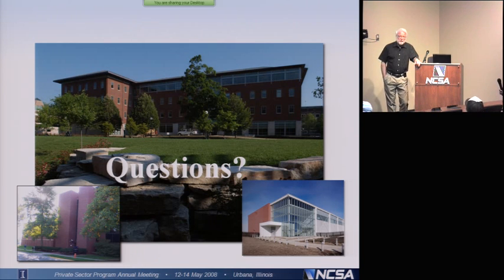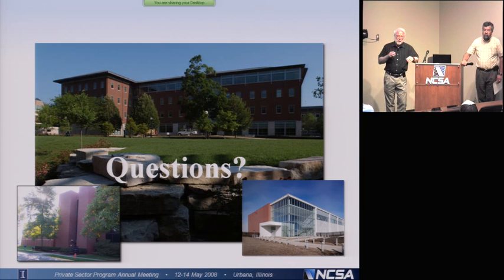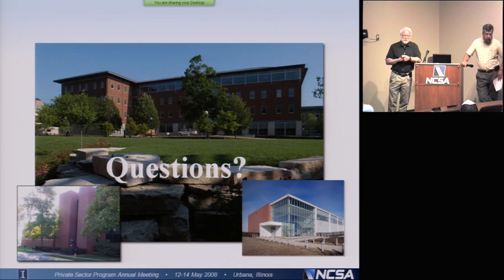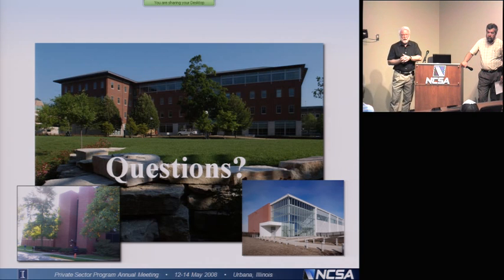The facility itself? Yeah. So one of the things we do is power conversion only once—we step the voltage that comes down. Blue Waters is fed by three separate electrical systems: one is the university's power grid, which can generate about 80 megawatts, and then two separate feeds from Ameren, our local service provider, coming from two different grids. We step the power down to the 480 volts used directly by the computers, and we only do that once, then everything is fed that 480 volts. That's an efficiency savings we have there.